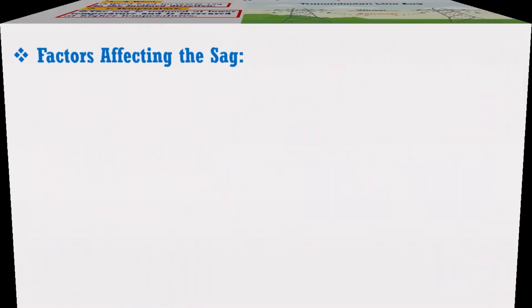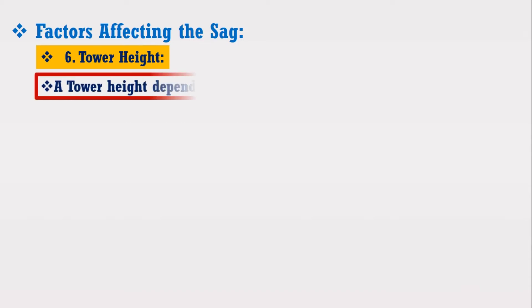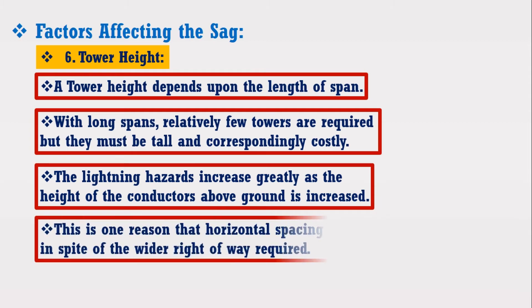6. Tower height: a tower's height depends upon the length of the span. With long spans, relatively few towers are required but they must be tall and correspondingly costly. The lightning hazard increases greatly as the height of the conductors above the ground is increased. This is one of the reasons that horizontal spacing is favoured in spite of the wider right-of-way required.